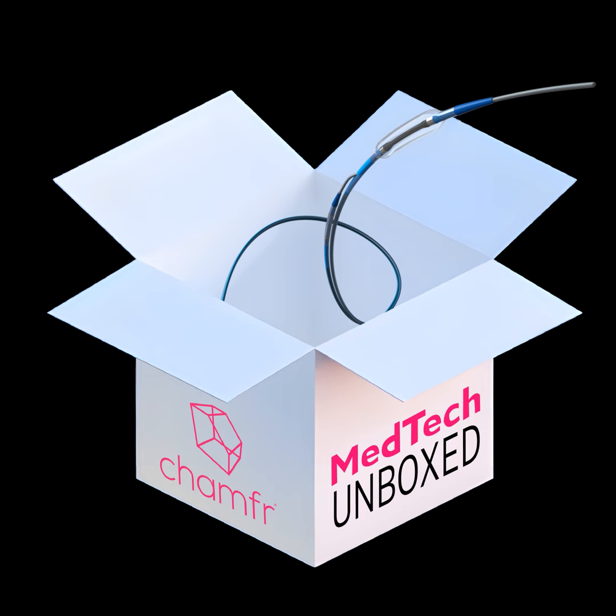Yeah. And then we also find a lot of interesting applications led by something like laser hypotube, where a lot of architecture is now going. For the longest time, the biggest challenge for people using laser hypotube is how to have a liner that's securely bound in the ID of the laser hypotube. Because it is PTFE, even if you etch it, it doesn't really bond to stainless steel. You have to count on the reflow window, the curve, or the jacket to sink in to bond to it, or you can add a tie layer, but those are not ideal choices because it will still tend to delaminate over time when you flex it.